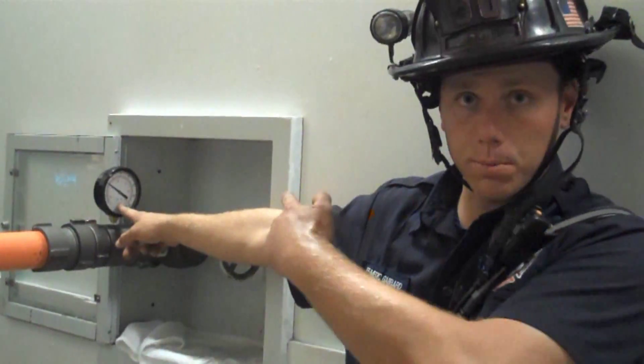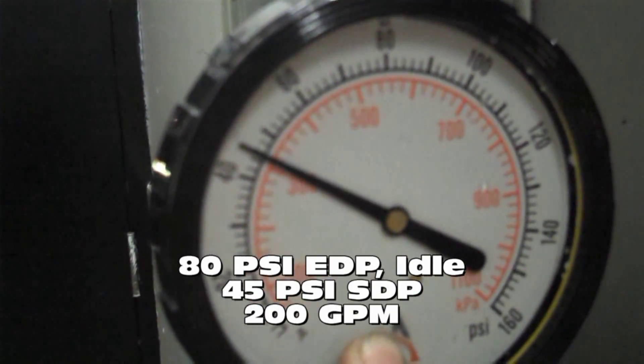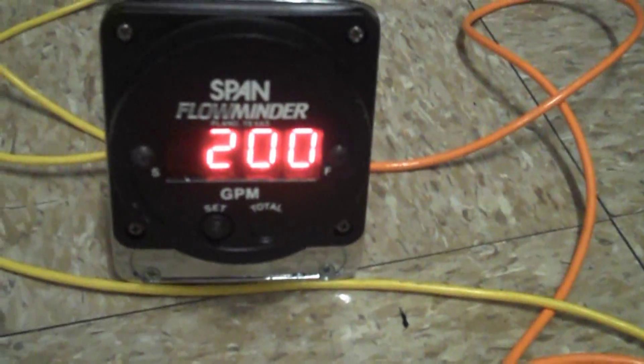Our riser discharge pressure is roughly 45 PSI — this is the engine pumping the standpipe at an idle. We're at 200 gallons a minute on the flow meter. At 80 PSI riser discharge pressure, I've got 260 to 270 gallons a minute flow, which will be the rated flow for that engine with a 1 1/8 inch tip.